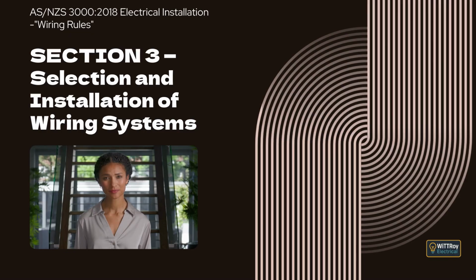Clause 3.5, Conductor size. This clause introduces the requirements that apply to the minimum physical size of conductors used in wiring systems. Clause 3.5.1, General. This clause states that the nominal cross-sectional area of conductors must not be less than the minimum values specified for the type of wiring system and the intended use of the circuit. These minimum sizes are set to ensure adequate current carrying capacity, mechanical strength, and reliable connections.